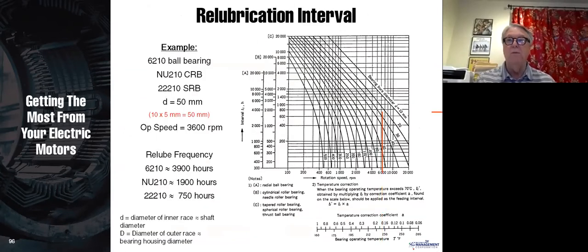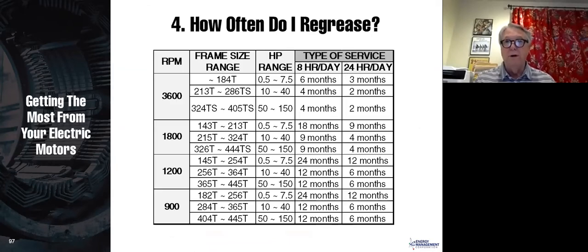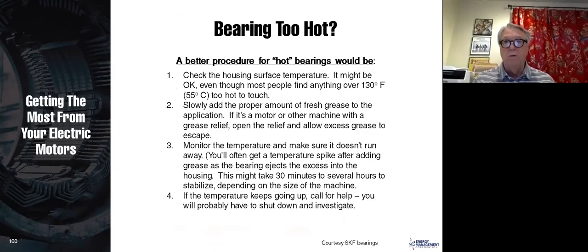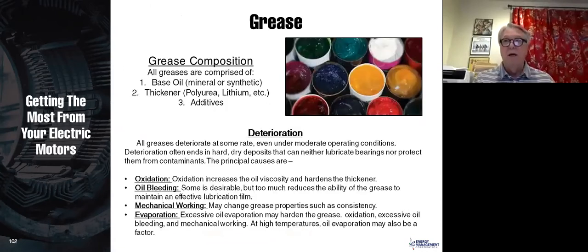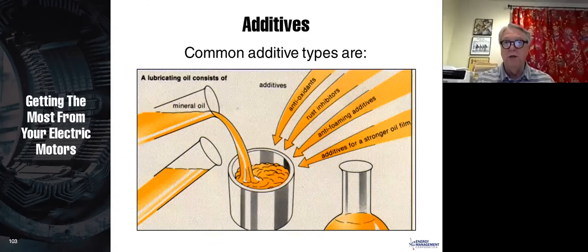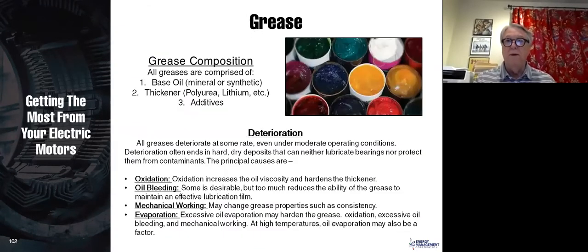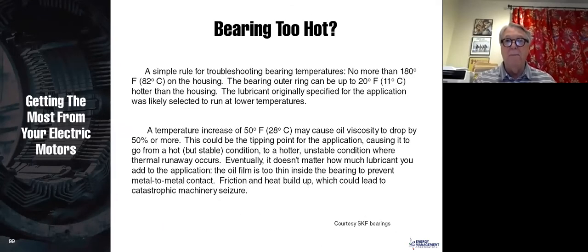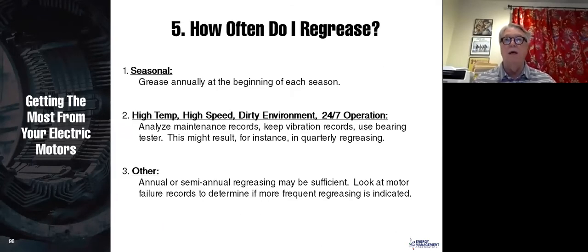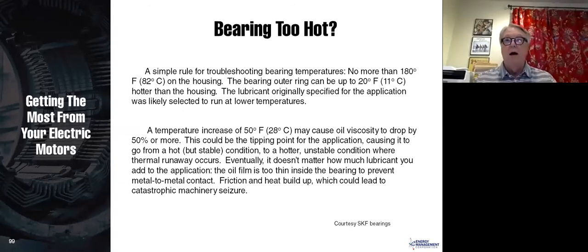Just one of the many problems you can get into with regreasing. And as you know, the number one reason for motor failure is bad bearings, and the number one reason for bearing failure is improper lubrication. Could be too much grease, too little grease, the wrong kind of grease, but mostly it's just greasing in the wrong way. So let's talk about right here. This is where we ended. How often do I regrease? Now, not only do you need to worry about the motor being too hot, but the bearings as well.